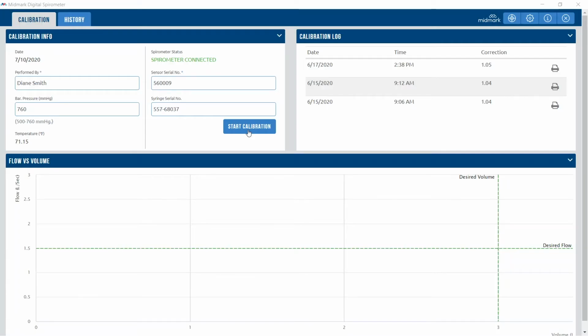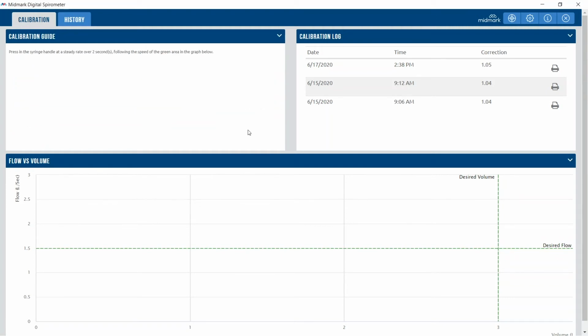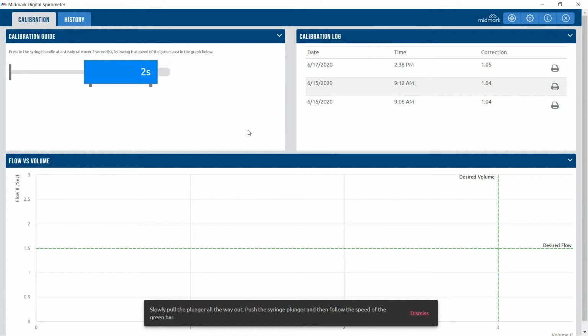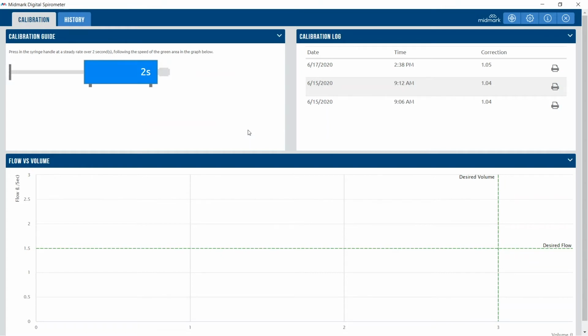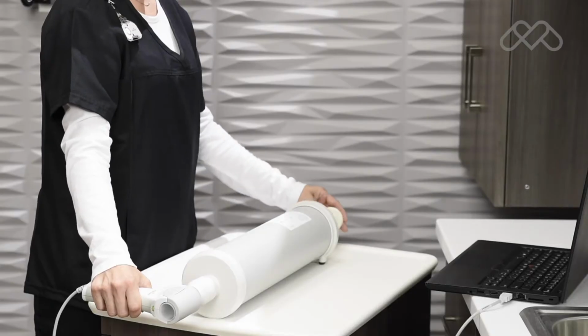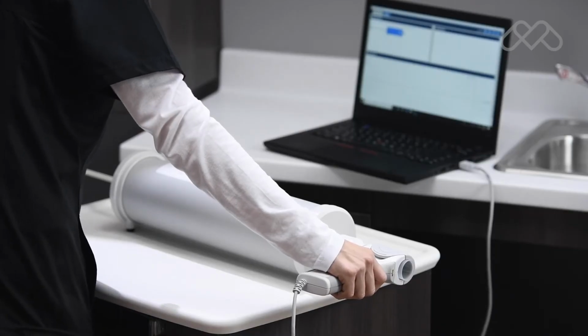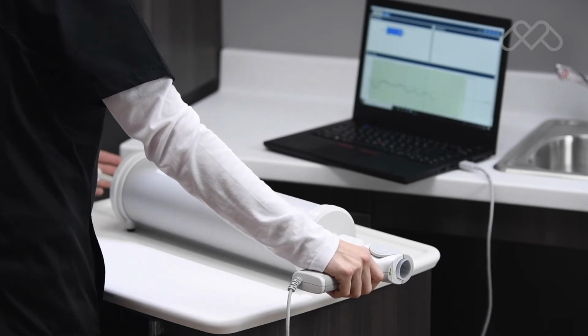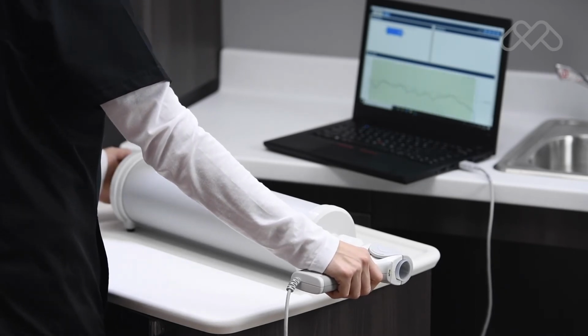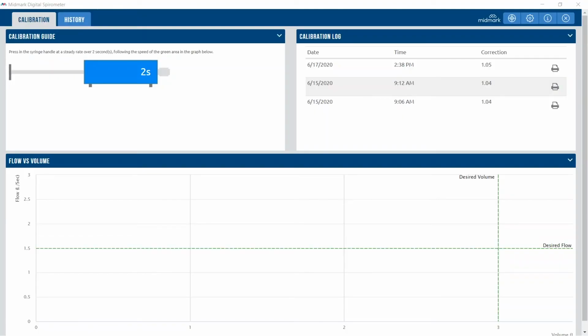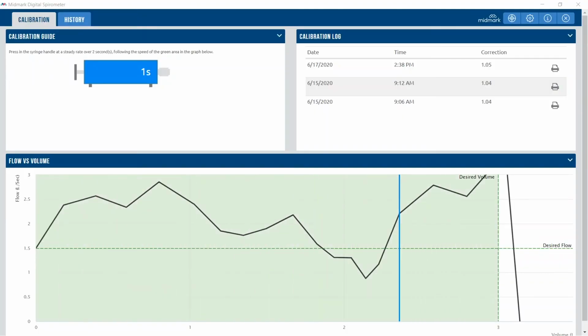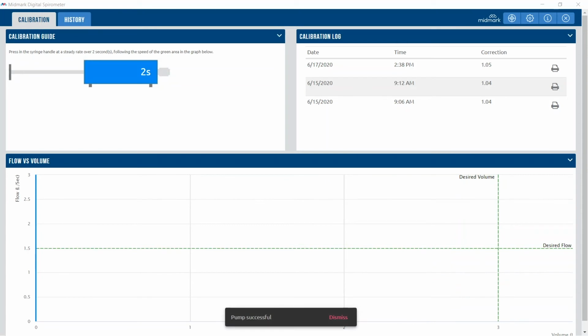After filling in the required fields for the calibration information section, click Start Calibration on the calibration screen to begin the calibration of the spirometer device. The sensor will zero itself, and then the calibration pump screen will appear. Pull the plunger all the way out and inject the air from the syringe into the spirometer. It is important to maintain a smooth, steady motion when performing the calibration. Use the dotted line and/or the moving green area on the volume versus time graph as a target flow rate.